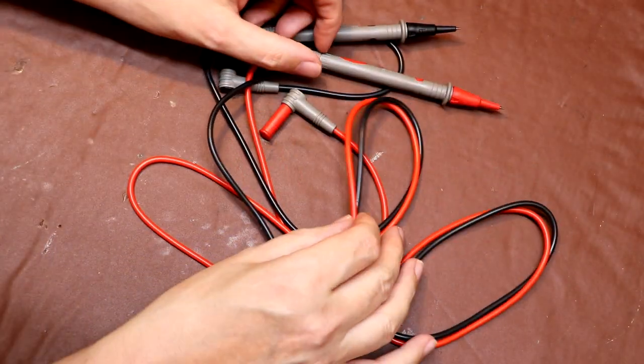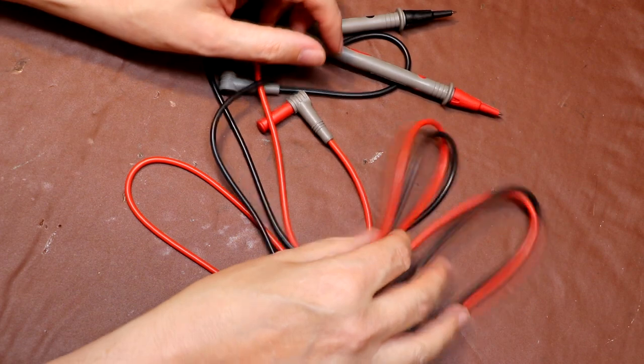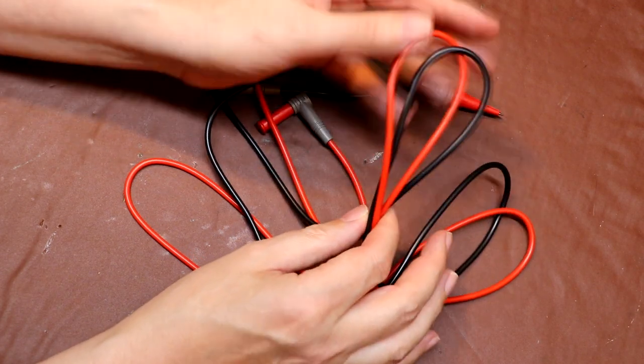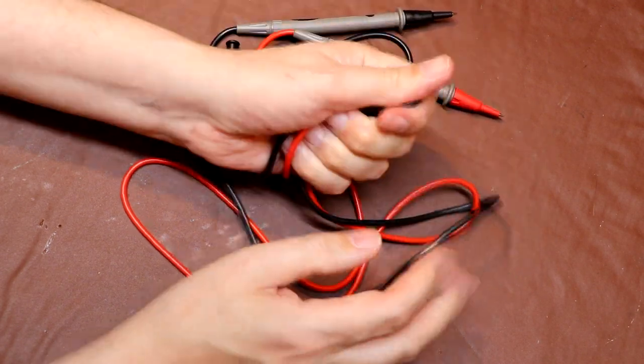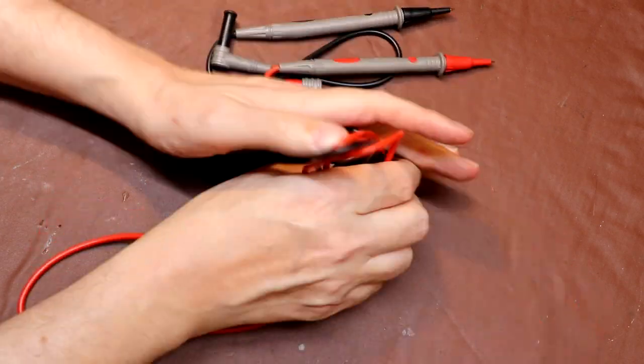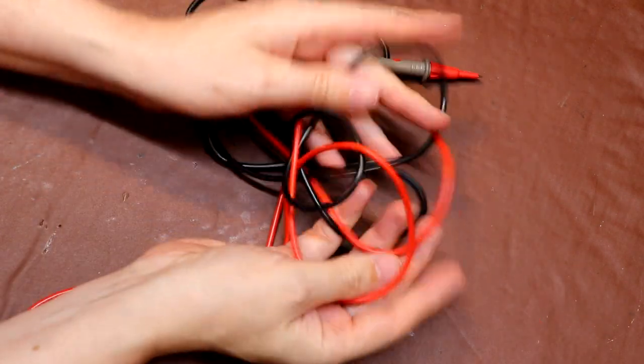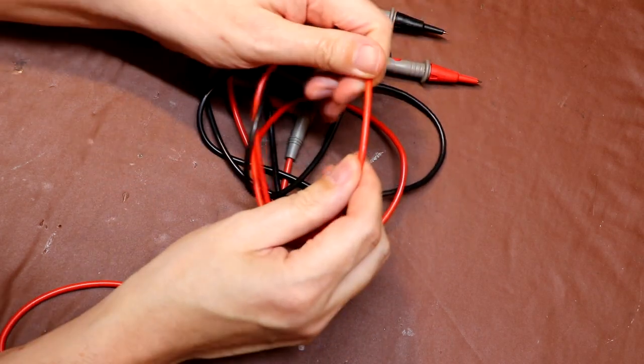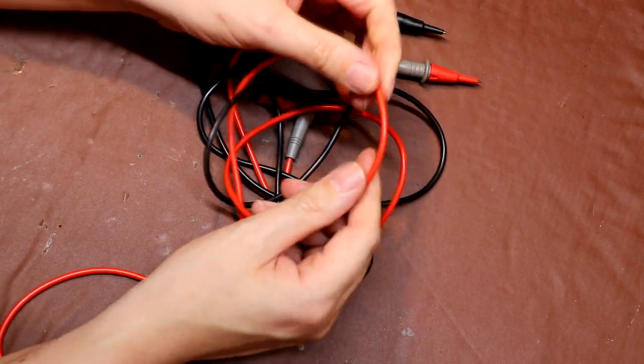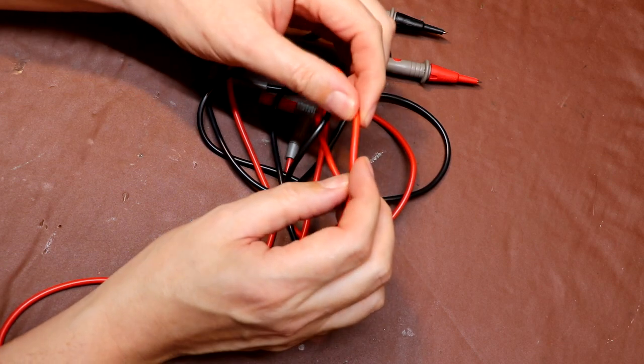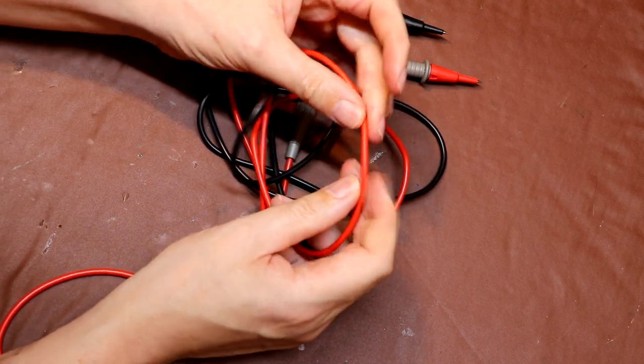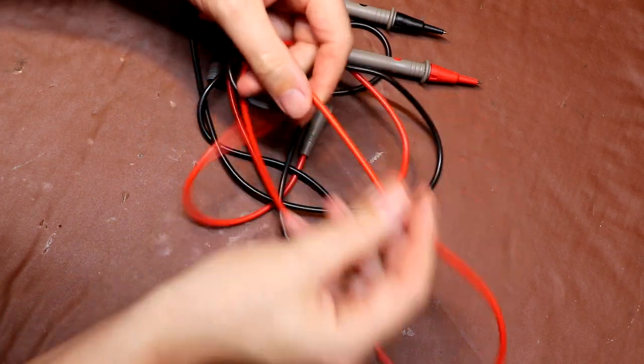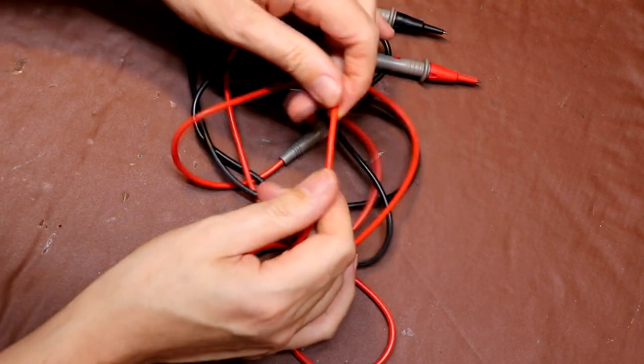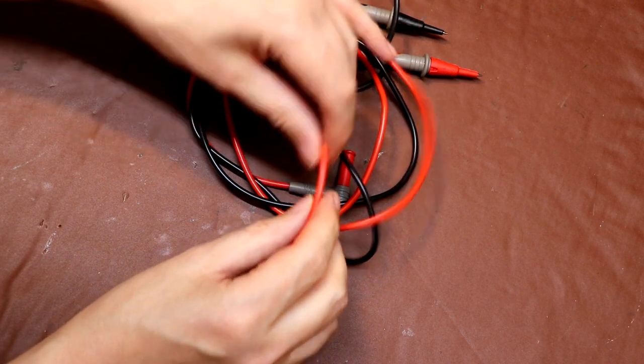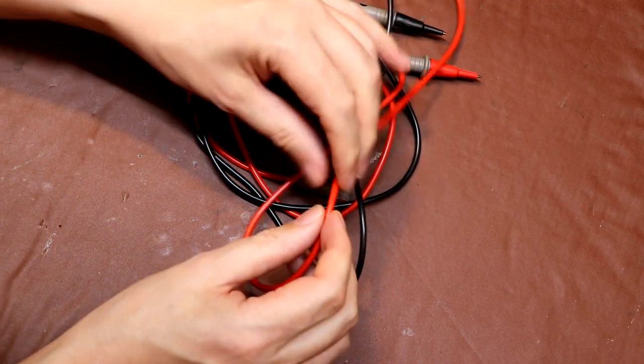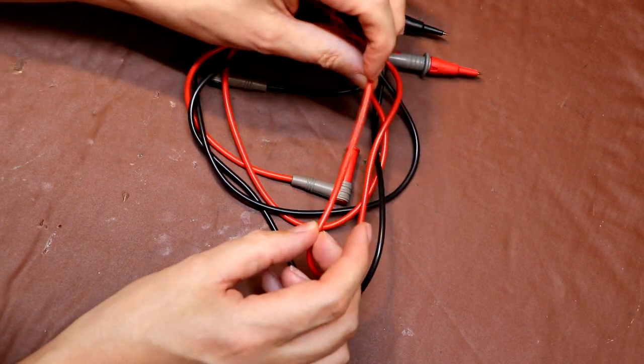Whenever you're doing a review of test meter leads, it is in fact the law that you have to do some flexibility testing of the cables themselves. And actually they feel absolutely lovely, super flexible, really soft. Now again, I'm wondering if these are actually silicone or if they're that plasticized, is it PVC they use? I'm not exactly sure. Have we got anything written on them? No, there's nothing actually written on the cable itself, which would have been maybe nice to have some information about the quality of the cable.